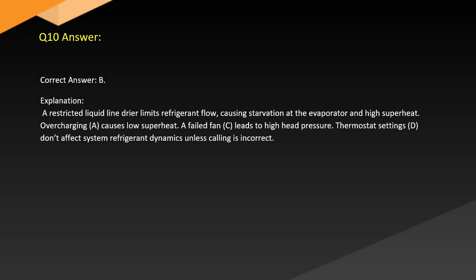Answer. Correct answer: B. Explanation: A restricted liquid line dryer limits refrigerant flow, causing starvation at the evaporator and high superheat. Overcharging, A, causes low superheat. A failed fan, C, leads to high head pressure. Thermostat settings, D, don't affect system refrigerant dynamics unless the call for cooling is incorrect.